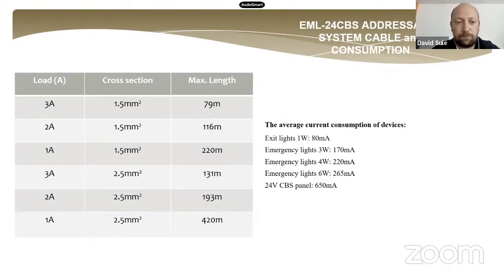So here's the cabling design information by different load. One circuit maximum load is 3 amp. When we have a 3 amp with 1.5 cable, the maximum cable length will be around 79 meter. If we check the 3 amp with 2.5, this is 131 meter. This table helps you during the design, but we have a Microsoft Excel calculation table where you can put all of the luminaires on the circuit, and it will calculate the maximum cable length with the maximum 4% voltage drop.